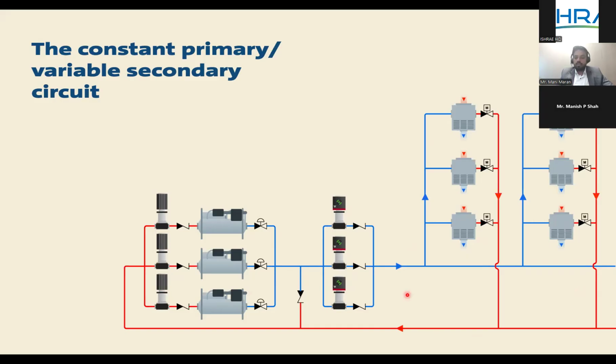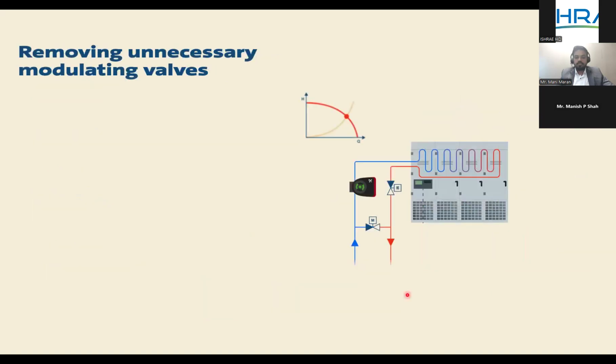Let's see how we can do this in a better way with distributed pumping. Before jumping into that, let's see how it impacts the pump performance, or where the savings are coming from on the pump side. So when we have a valve-based system, this is the pump curve. We have flow on the x-axis, head on the y-axis, and this is the pump curve at full speed. This is the system curve, where it starts from zero, based on the closed loop system and the differential pressure across the critical load at full speed. Your control curve may vary for each system, and it depends on the system and the requirement.